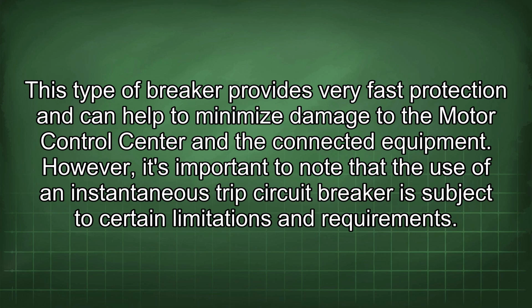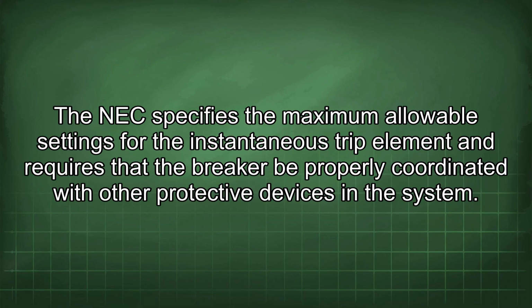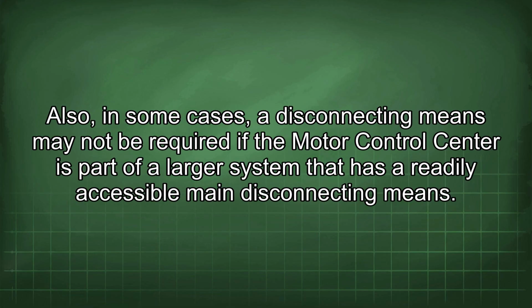However, it's important to note that the use of an instantaneous trip circuit breaker is subject to certain limitations and requirements. The NEC specifies the maximum allowable settings for the instantaneous trip element and requires that the breaker be properly coordinated with other protective devices in the system. Also, in some cases, a disconnecting means may not be required if the motor control center is part of a larger system that has a readily accessible main disconnecting means.